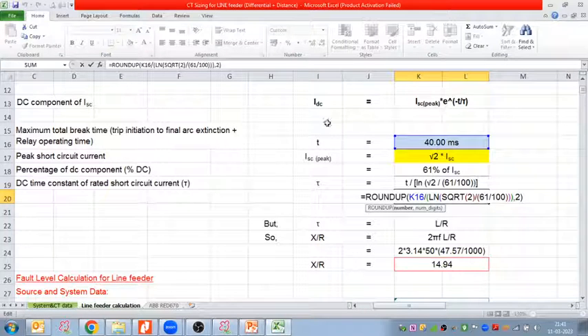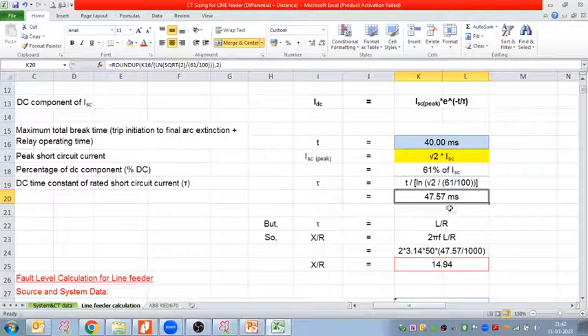again IDC is how much? 61 percent of ISC. So under root 2 ISC divided by 61 percent ISC. So ISC will be cancelled out, and only 61 percent will remain here, right? And this T would be on top. So 40 divided by this much, and we are rounding to 2 digits. So the final value comes to 47.57 millisecond. So this is the time required to decay the DC component from the circuit.